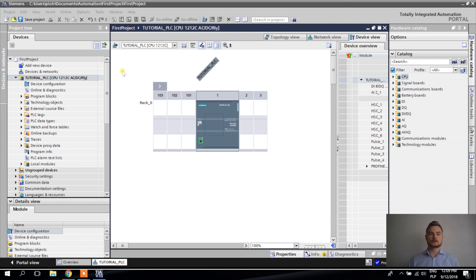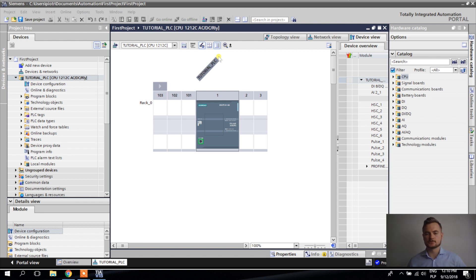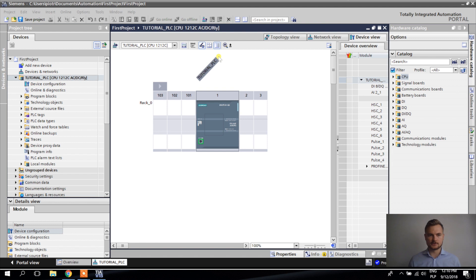The window that opened is Device Configuration, which is the equivalent of hardware configuration in old Step 7. Here we can configure different settings for our PLC. If we have additional input/output modules, drives, gateways, or encoders for position data, all that hardware is configured here in device configuration as well. Since we only have the PLC right now, I'm going to close it and show you more later.